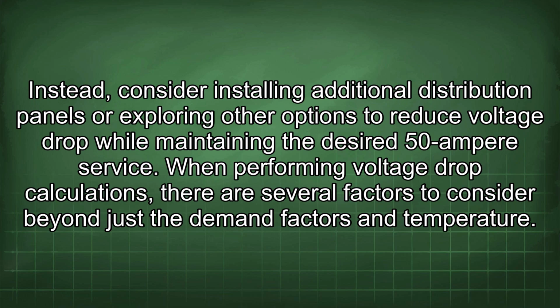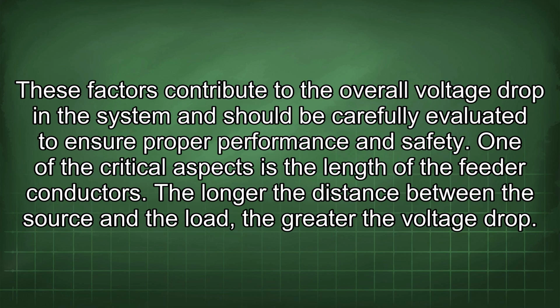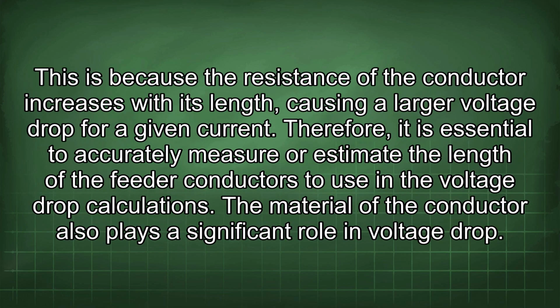When performing voltage drop calculations, there are several factors to consider beyond just the demand factors and temperature. These factors contribute to the overall voltage drop in the system and should be carefully evaluated to ensure proper performance and safety. One of the critical aspects is the length of the feeder conductors. The longer the distance between the source and the load, the greater the voltage drop. This is because the resistance of the conductor increases with its length, causing a larger voltage drop for a given current.